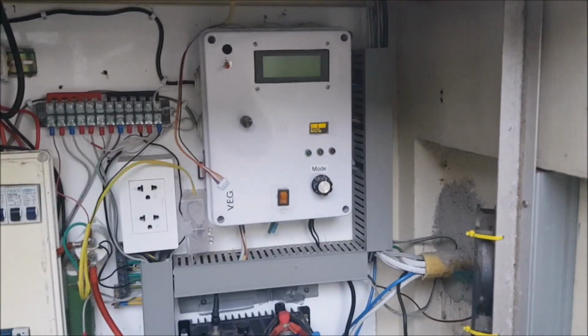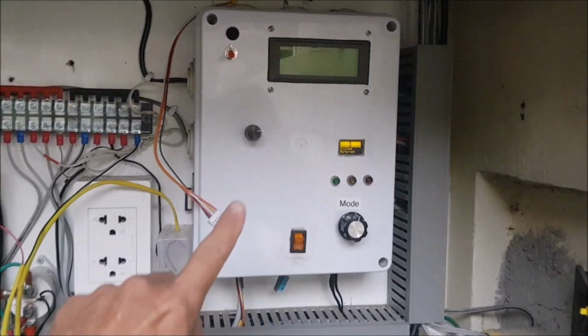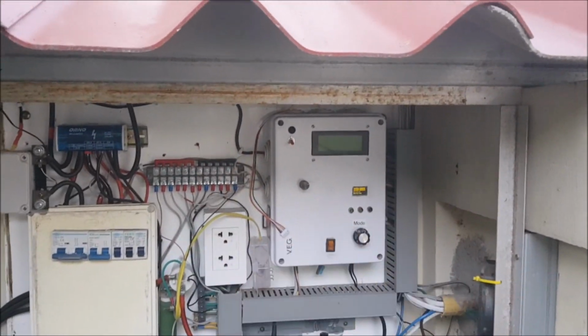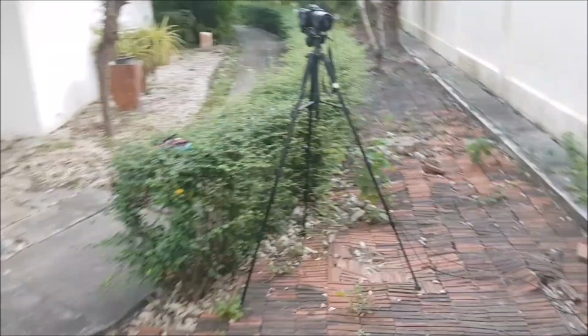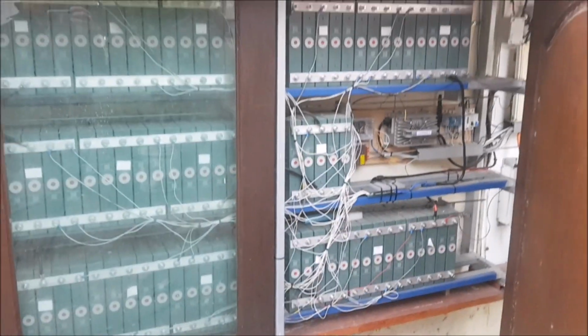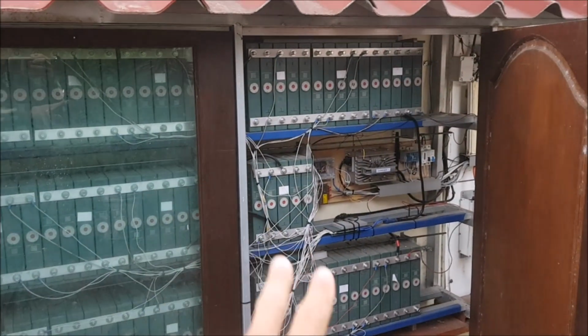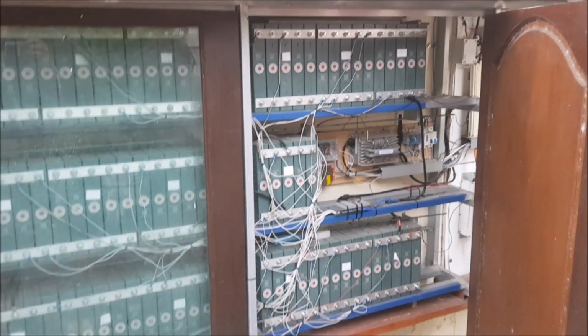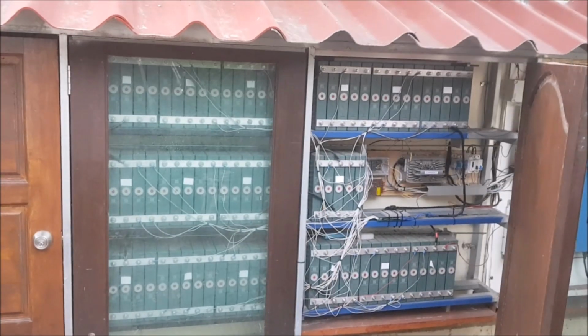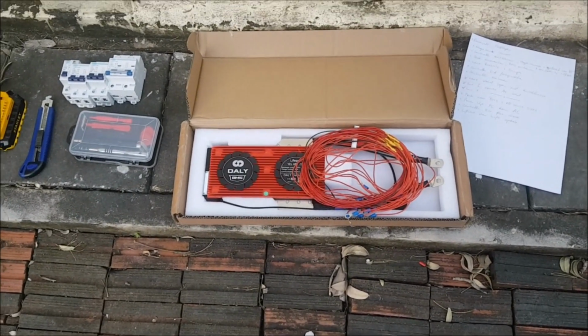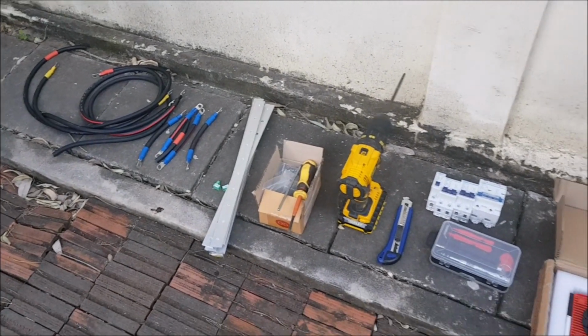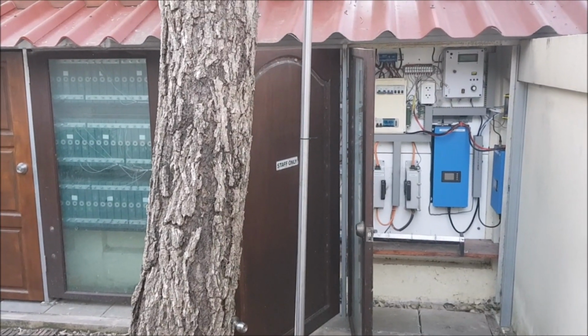What will be done now is remove the controller, take off all the wiring, and then we'll work on the DC side here, removing all those small wires. I will then rebuild this pack so that it can cope with the new performance situation. We will install the new BMS, new breakers, jumpers, wires, and bus bars. Let's do this - in around 1 hour this will already look quite different here.